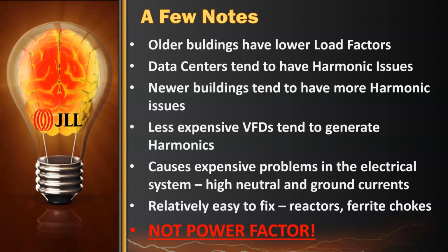Newer buildings typically tend to have more harmonic issues. That's because they have larger VFDs in them, some on the chillers, some on the motors, things of that nature. And less expensive VFDs tend to generate more harmonics, and that's a fact. They don't have filters on them. They don't have any sort of capture circuits or regenerative circuits, and so that harmonic gets generated, and it'll either go into the ground or, usually, it's fed back into the system. That's usually the way it winds up going.